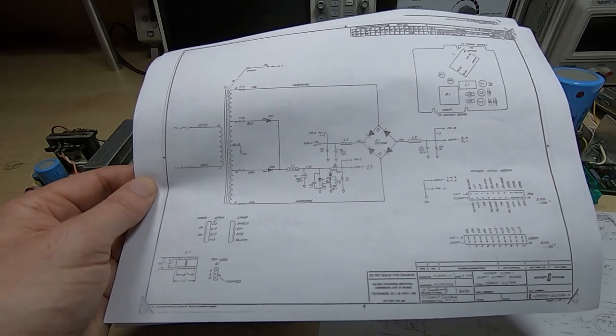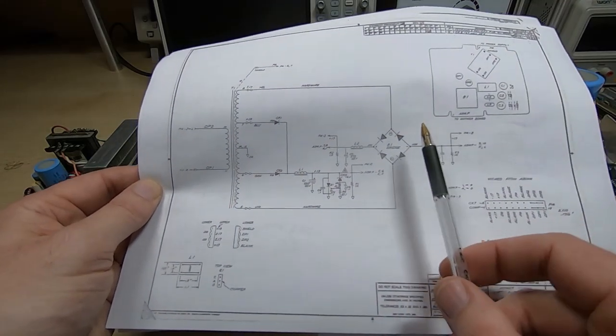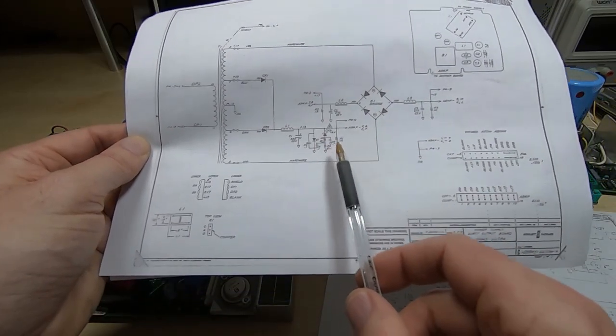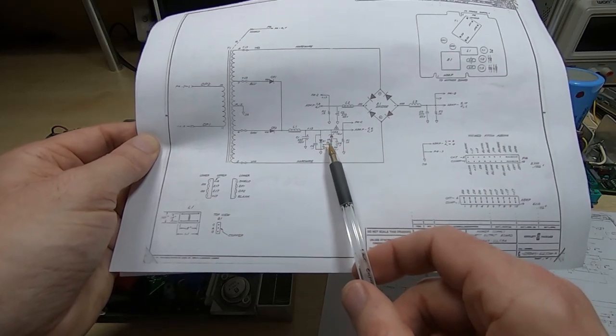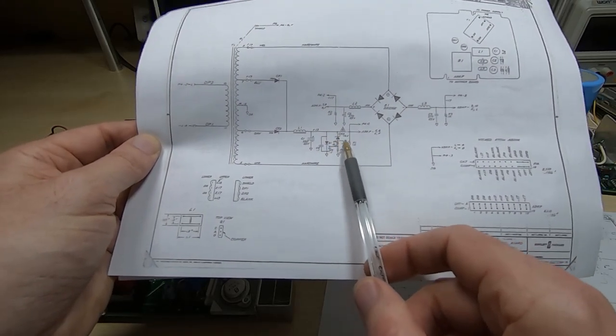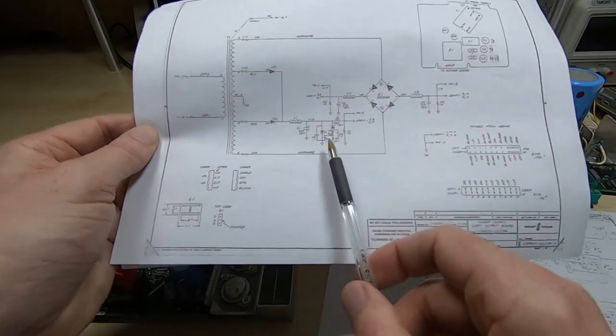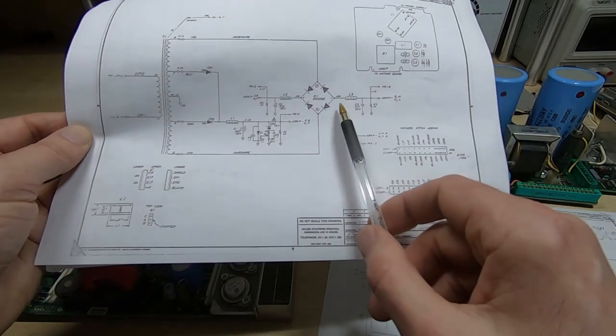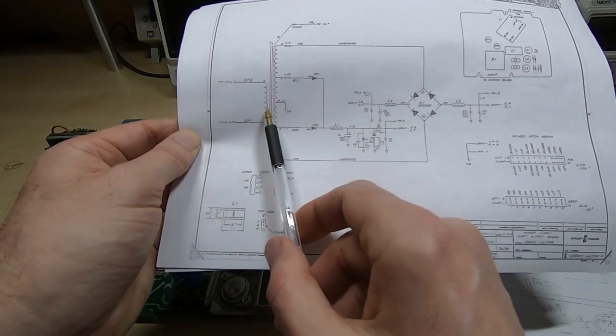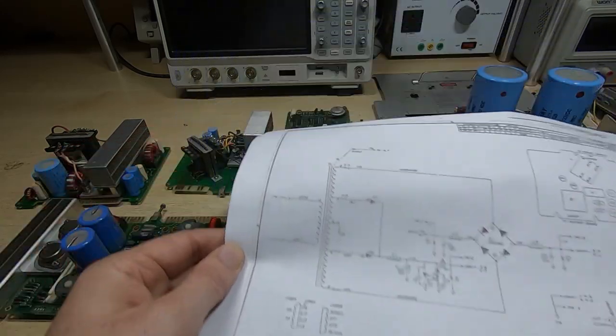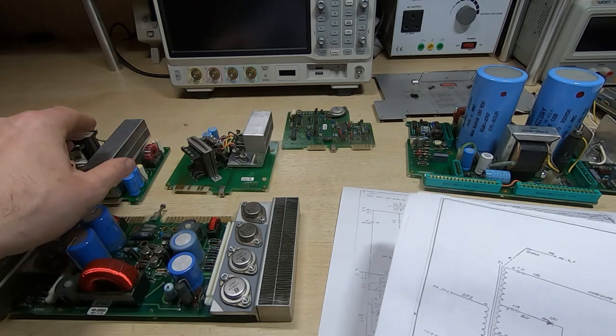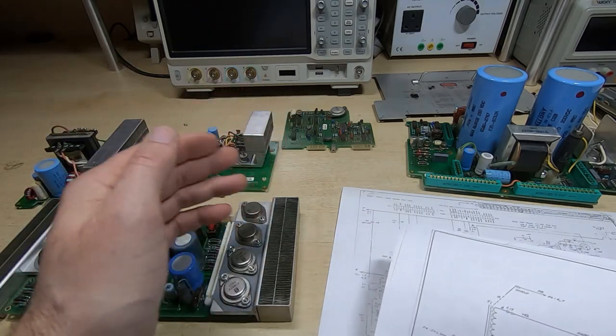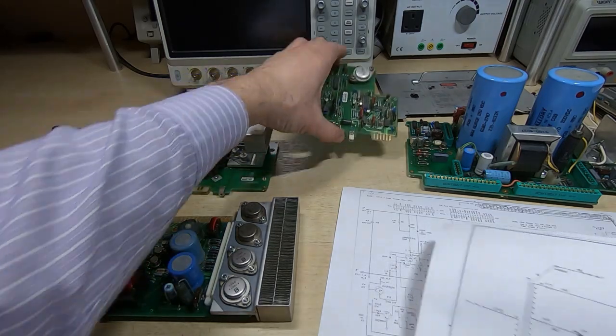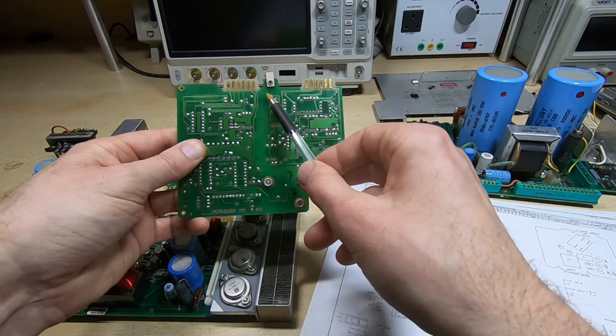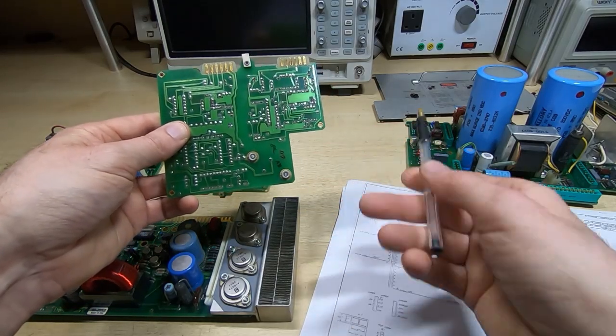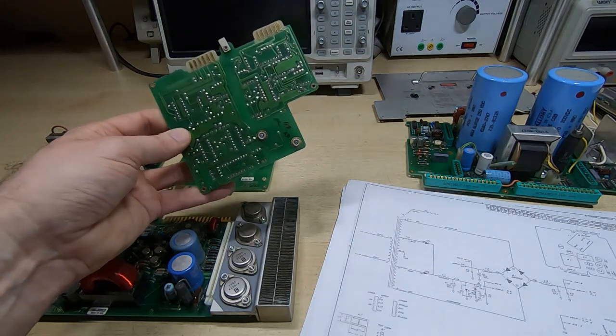Somebody asked if there's any crowbar protection on this power supply, and the answer is no, it doesn't actually need it. There are a couple of crowbars on the lower voltage supplies, but that's just because they are low energy supplies, and if something happens on these, it's not enough to shut down the entire supply, so they put separate crowbar protection. But the main rails don't need it because there is no direct DC path between input and output. In fact, if you look at the boards, you'll see very distinct separation gaps - for example on the regulator board, down the center we've got this isolation gap, because we've got effectively mains on one side and our output DC supplies on the other side.